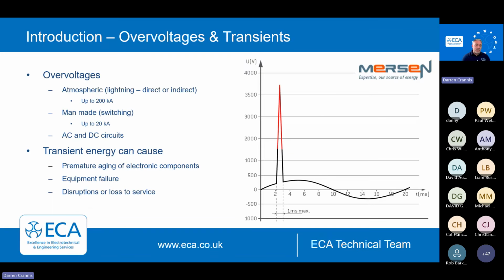This is very kindly given to us by our friends at Mersen, and we're going to talk briefly about what sort of things SPDs do. Now, everyone associates SPDs with the lightning standard, and that's 62305. Although we help implement that in BS 7671, our wiring standard, what we do is all about the Type 2, the man-made. But I'll give you an overview of this all. Transient overvoltages are voltage surges that can reach tens of kilovolts in just a matter of microseconds. Now, with lightning, we can get up to 200 kA of energy. That's in the worldwide standard.